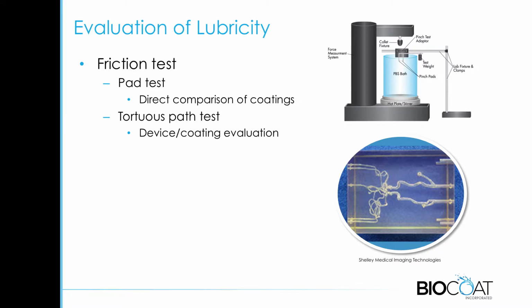but then if you want to simulate what's going into the body, you'd have what I call a tortuous path test, which is a simulation of the anatomy in the body, for example, a neurovascular anatomy. That looks at both the device and the coating together, and you can evaluate that. In seeing how well the ease of insertion works, you can measure the force that it takes to apply that. That goes for the initial friction. Then if you're doing multiple cycles on that, you can look at the durability for that device.